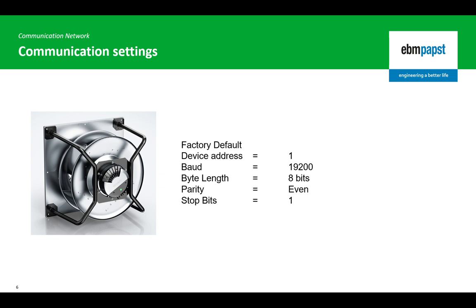If we're installing many fans on an RS485 communication network, we need to ensure that each fan has a unique device address. We also need to make sure that the baud rate, parity, and stop bits are the same for both the client and all server devices on the network to ensure successful communication.